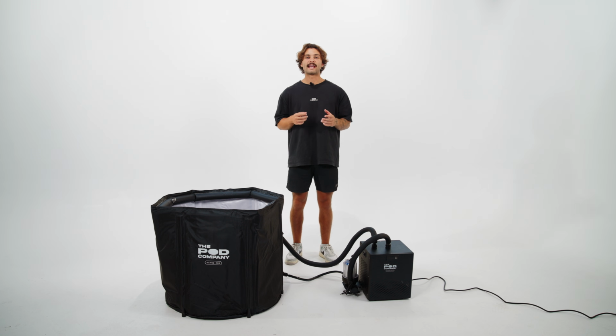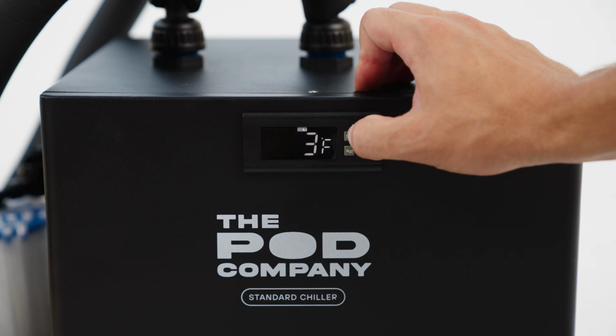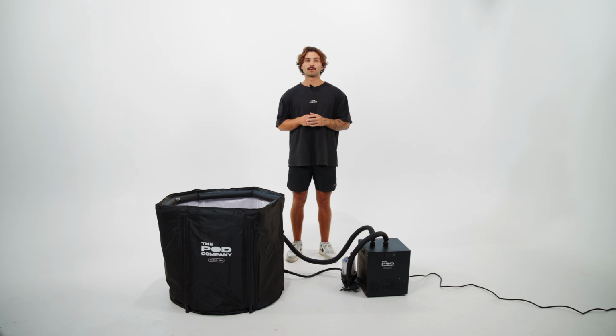Your chiller is now up and running, but let's talk about the F1 setting, which plays a crucial role in controlling how frequently the compressor activates. By default, F1 is set to +3 Fahrenheit, meaning the chiller will wait for a 3-degree increase in temperature before it starts cooling again.